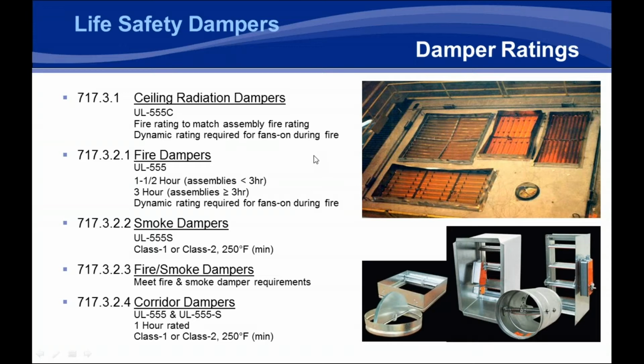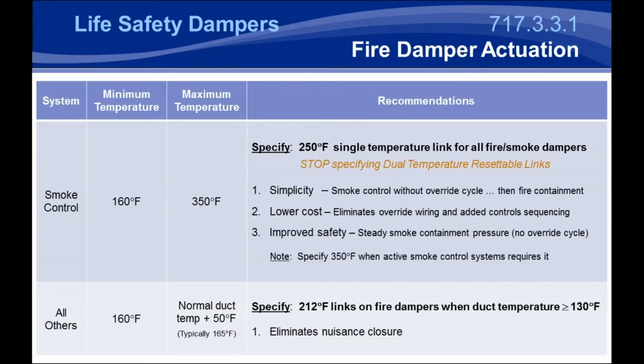The only other change to the types of life safety dampers is the code adding tunnel type corridors, which I won't spend too much time on since this presentation is geared primarily to the East Coast, and tunnel type corridors are primarily only seen in California and on the West Coast. But they have been added to the code, and I will explain them a little bit later in less detail than some of the other corridors. For fire damper actuation, there's basically two classifications the code has. Basically, all fire dampers that are used in smoke control systems, and then fire dampers that are used everywhere else in the building, not in smoke control systems.